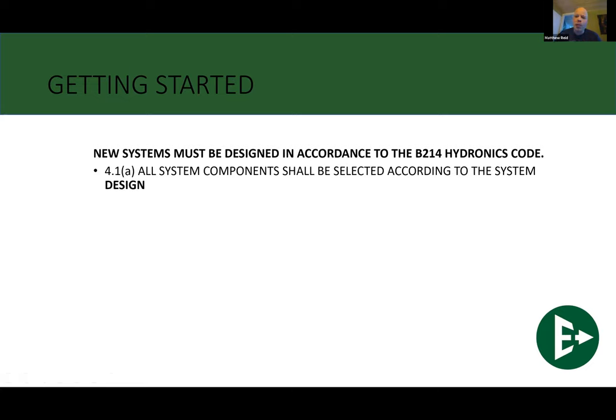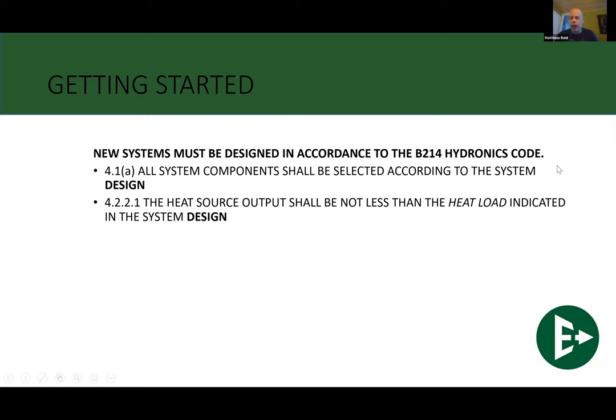All system components shall be selected according to the system design. So when you are getting your system design done, whether you're doing it by yourself or getting a designer to put it together for you, all components shall be selected according to the design of the system, meaning that you're not going to have over pumping, or a boiler that's way too large or too small. Select the components that have been designed to work with all these pieces. This is kind of a no-brainer, but it comes up more often than you think. The heat source output shall not be less than the heat load indicated, meaning that, basically, don't undersize the boiler.